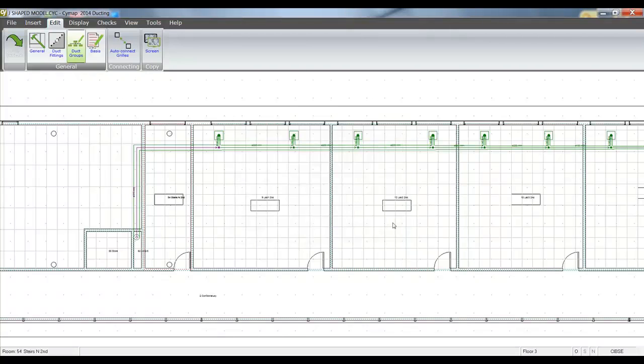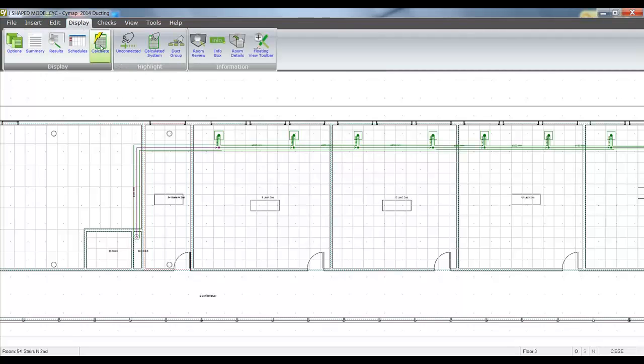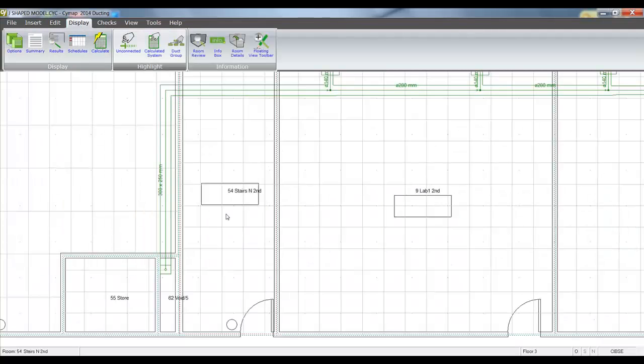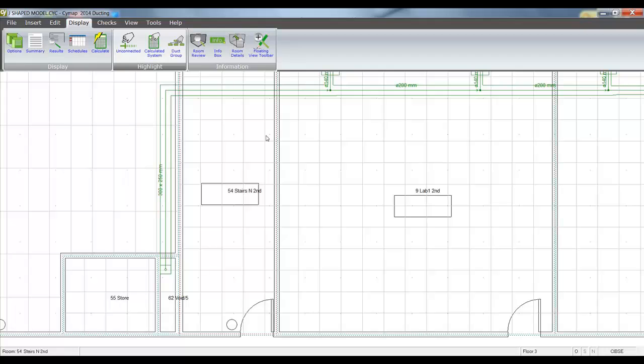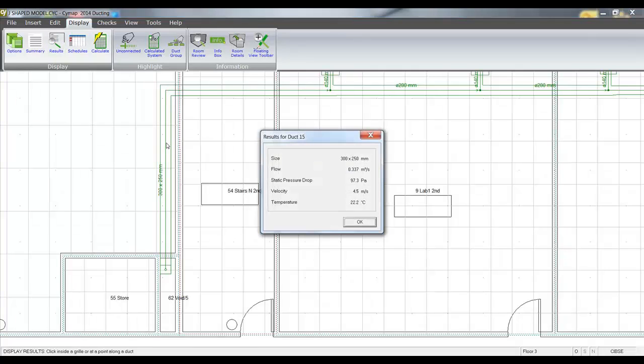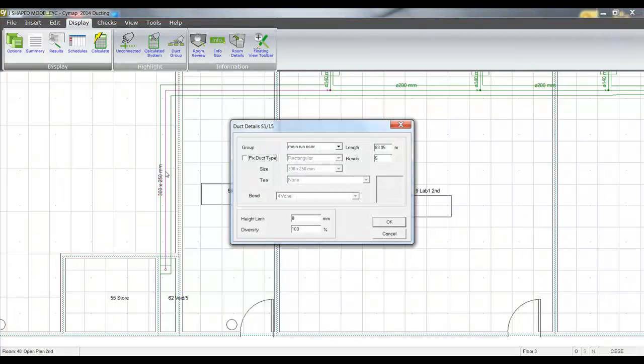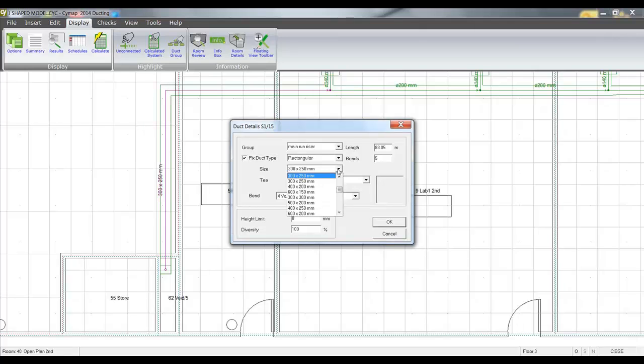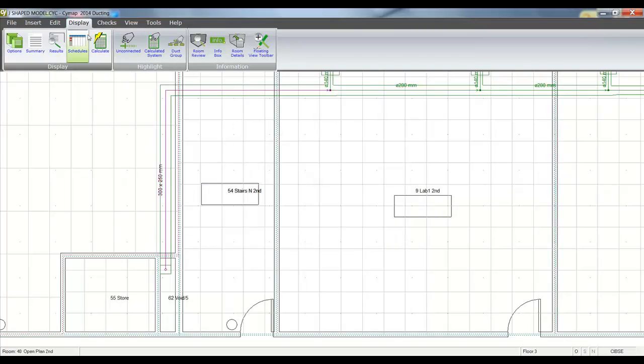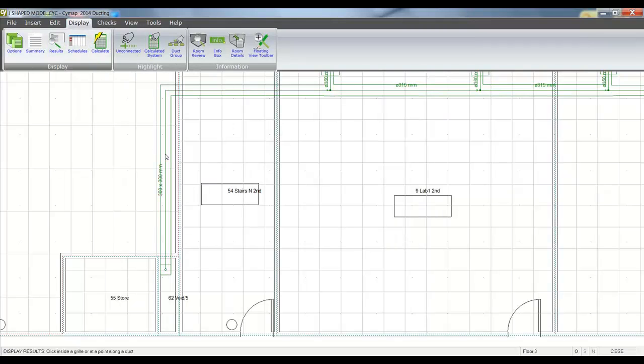There are many shapes and sizes of rectangular ducts in the duct database. If I run a calculation and I'm not happy with the size it's given me, I can make a change. So I could look at changing that 300 by 250, bearing in mind I'm connecting onto 280 diameter. I could look at the results of that piece of duct. That gives me a velocity of 4.5 meters per second. I might actually wish to change that size. If I double click on that, I can then go and fix it. Let's make it a 300 square. Calculate and run the results.